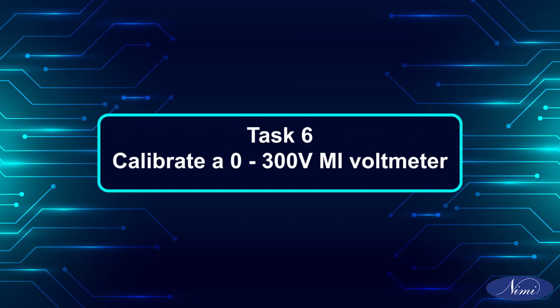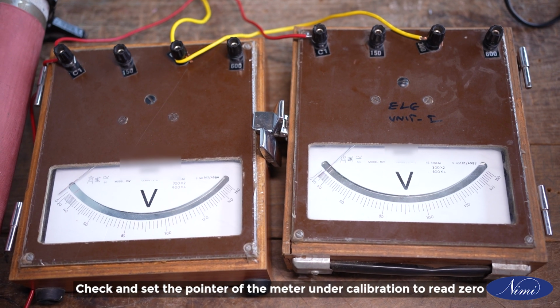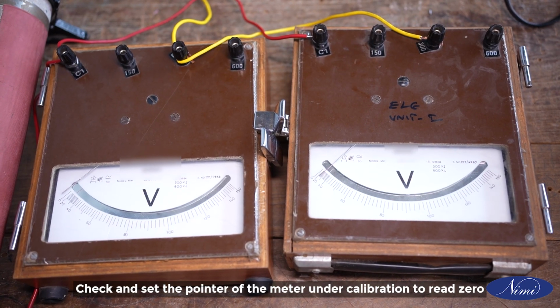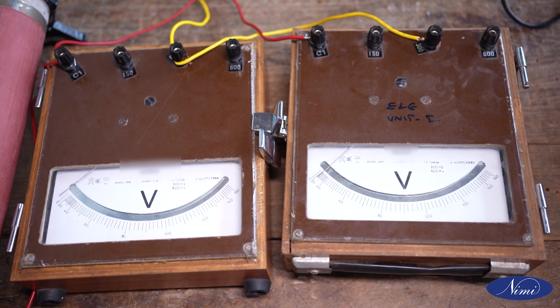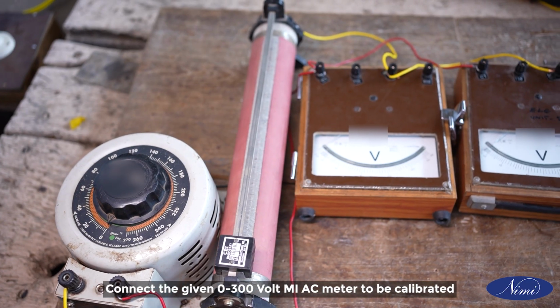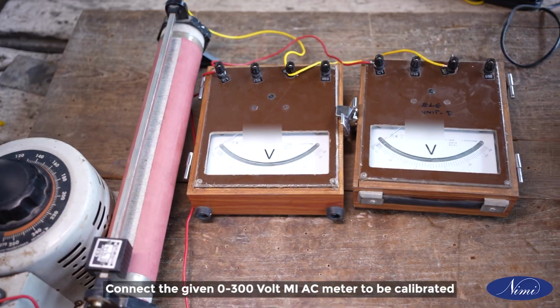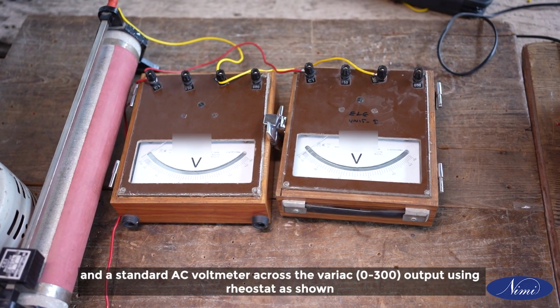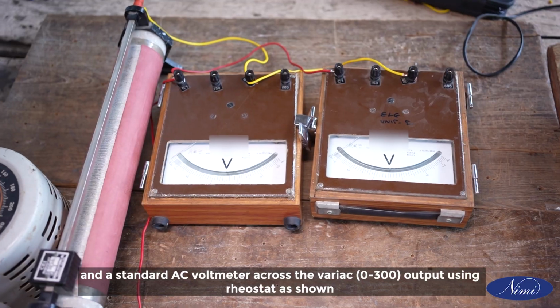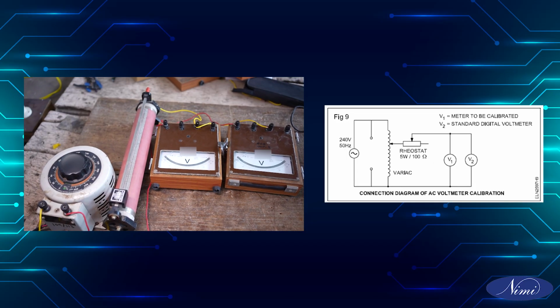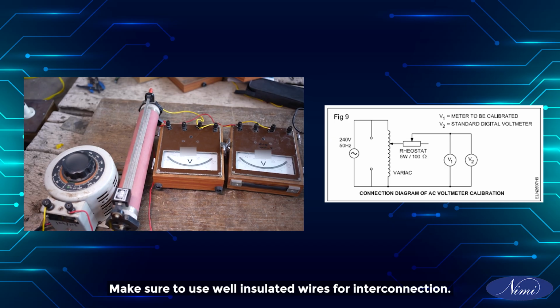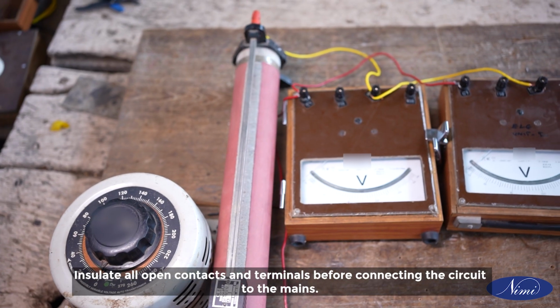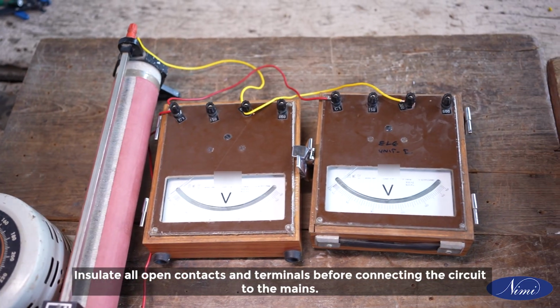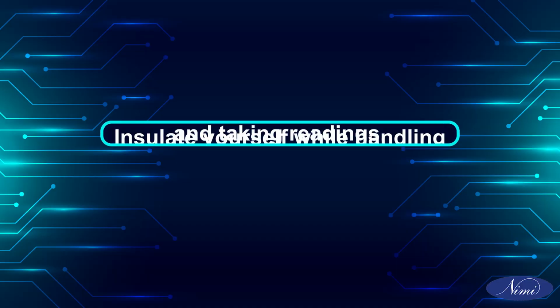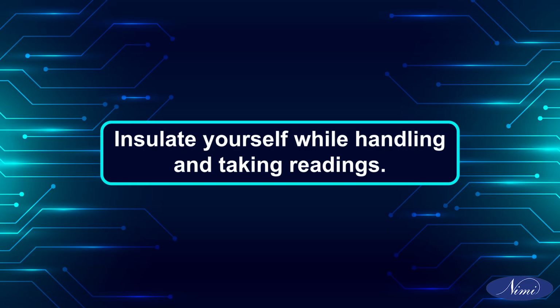Task 6. Calibrate a 0 to 300 volts MI voltmeter. Check and set the pointer of the meter under calibration to read 0. Connect the given 0 to 300 volt MI AC meter to be calibrated and a standard AC voltmeter across the variac output using rheostat as shown. Make sure to use well-insulated wires for interconnection. Insulate all open contacts and terminals before connecting the circuit to the mains. Insulate yourself while handling and taking readings.